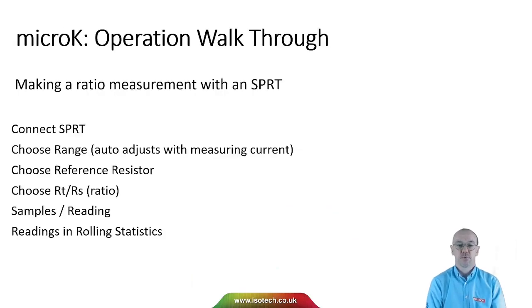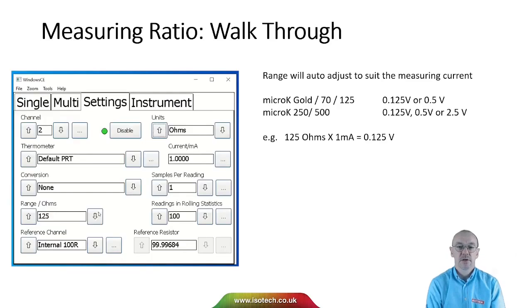Let's take a walk through on how we might measure ratio measurement with an SPRT. Very simple: connect the SPRT, choose the range, choose the reference resistor, set ratio, and we've got optional values for the statistics. Let's see how that looks. So I've got a default PRT, don't need any conversion here. I want the 125 ohm range at 1 milliamp. I'm going to use the internal 100 ohm reference resistor. So here for units I just select RT over RS and we're good to go.